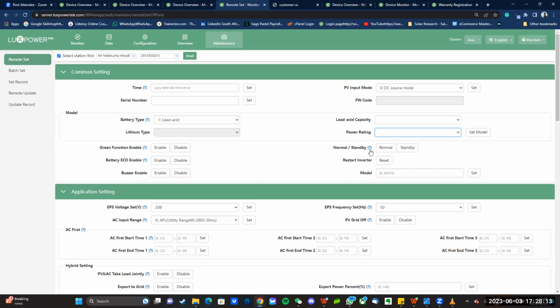Your normal and standby, in most cases, it'll be on normal. Just a bit of a heads up, I have dealt with the situation with the unit on standby. If left on standby for too long, you're going to get an overheating warning or a temperature, I can't remember the exact wording, but it's temperature something. That will appear on the Luxpower because on standby the fans are not going to be spinning, but the components inside are still heating up.